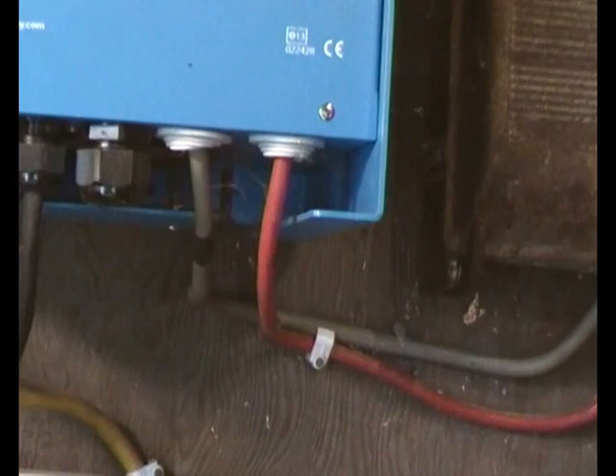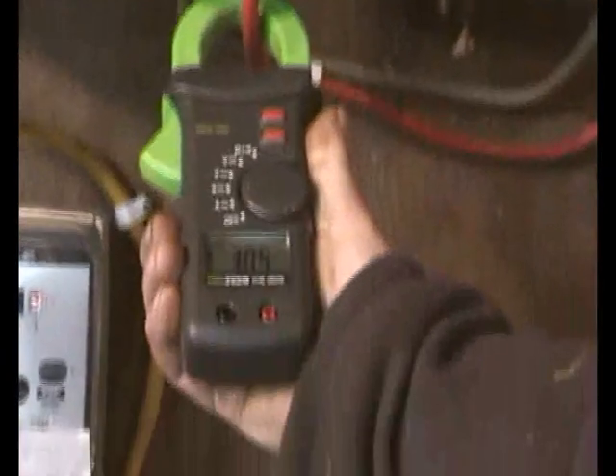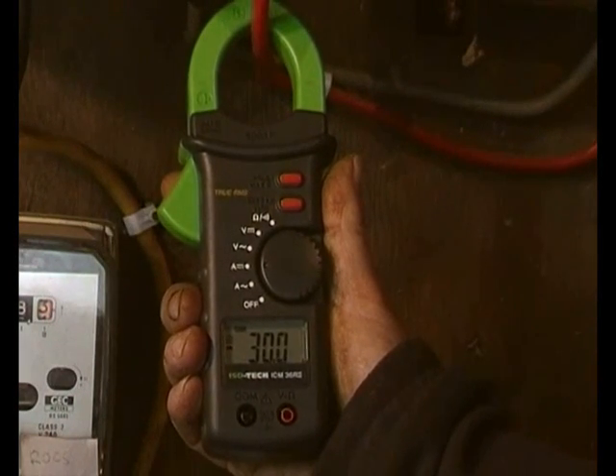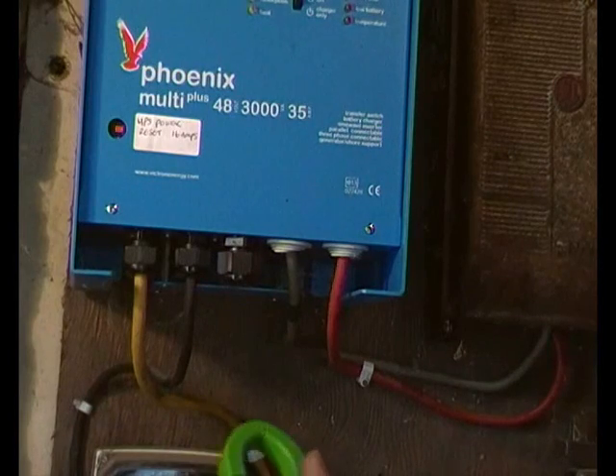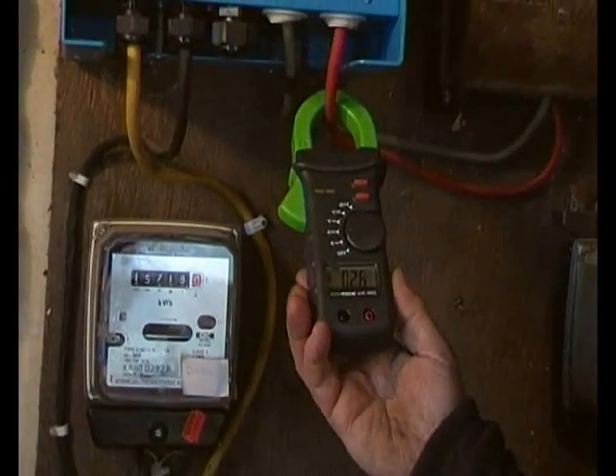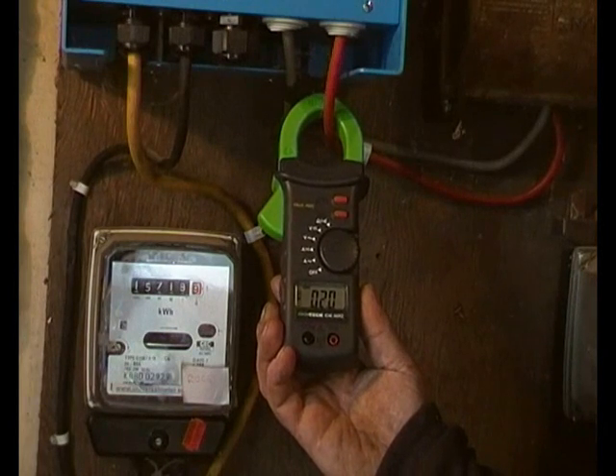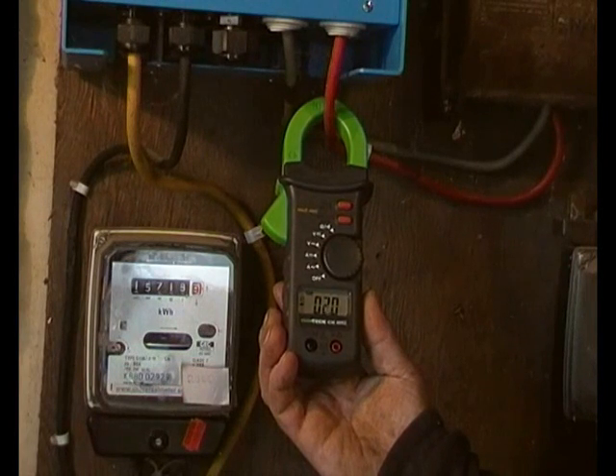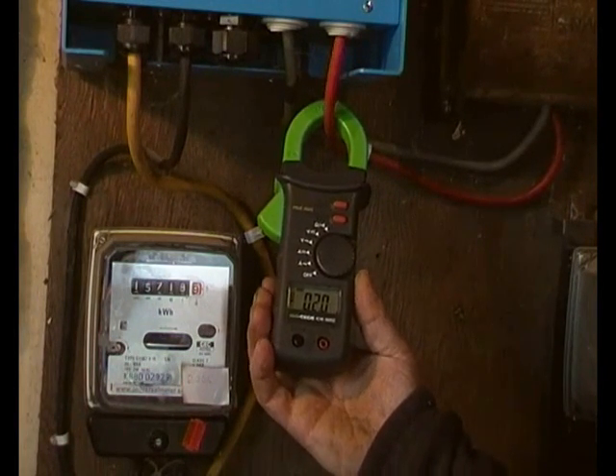Because we've got a load on the inverter, let's just see what that's drawing. There's the positive — 30 amps, one and a half kilowatt. So the load's gone off the inverter now. Let's just see what it shows — 2 amps. That's the sort of background with a few lights maybe, the boiler computer, what have you. And it'll go up a bit if say the fridge or freezer comes on, and then of course big loads will draw a lot more current.